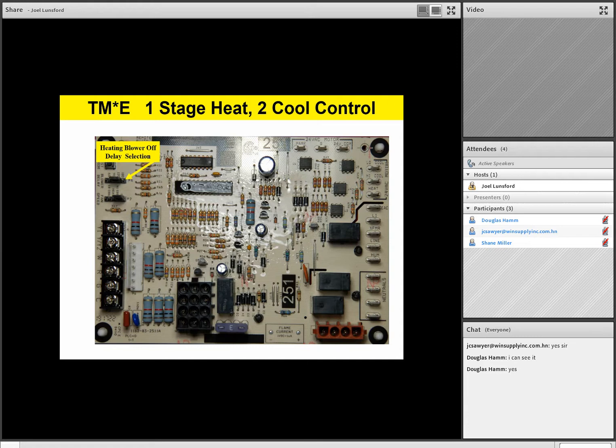Right above that is the last error button. That last error button allows the technician to pull flash codes off the board, and it remembers the last 5 faults. Now it should be noted, if the technician should hold that button down for about 10 to 15 seconds, it'll clear the memory.